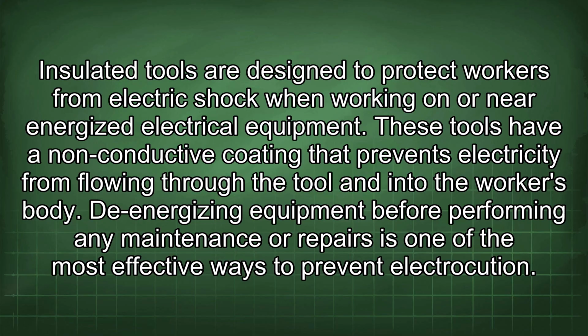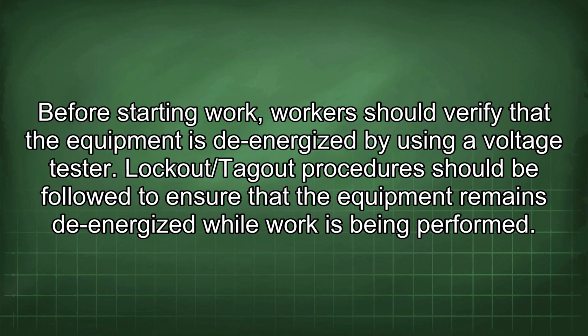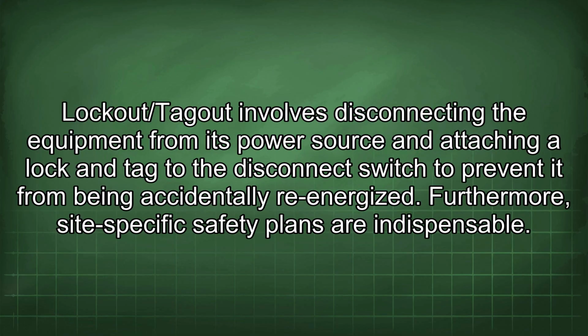Insulated tools are designed to protect workers from electric shock when working on or near energized electrical equipment. These tools have a non-conductive coating that prevents electricity from flowing through the tool and into the worker's body. De-energizing equipment before performing any maintenance or repairs is one of the most effective ways to prevent electrocution. Before starting work, workers should verify that the equipment is de-energized by using a voltage tester. Lockout/tagout procedures should be followed to ensure that the equipment remains de-energized while work is being performed. Lockout/tagout involves disconnecting the equipment from its power source and attaching a lock and tag to the disconnect switch to prevent it from being accidentally re-energized.